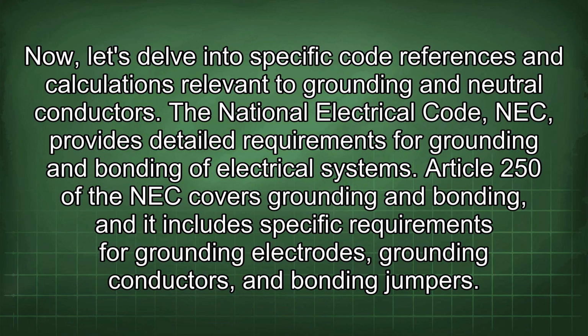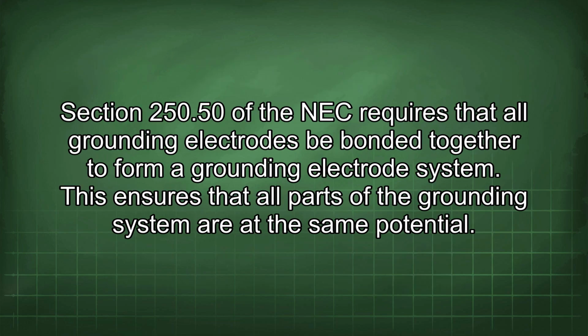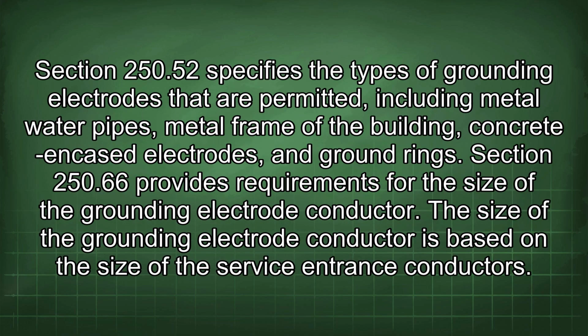Now let's delve into specific code references and calculations relevant to grounding and neutral conductors. The National Electrical Code, NEC, provides detailed requirements for grounding and bonding of electrical systems. Article 250 of the NEC covers grounding and bonding, and it includes specific requirements for grounding electrodes, grounding conductors, and bonding jumpers. Section 250.50 of the NEC requires that all grounding electrodes be bonded together to form a grounding electrode system. This ensures that all parts of the grounding system are at the same potential.